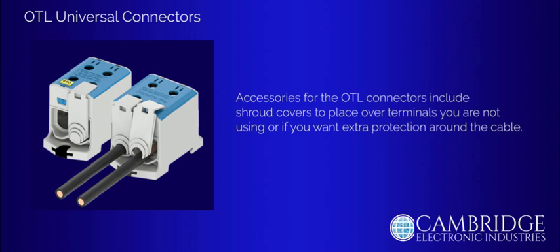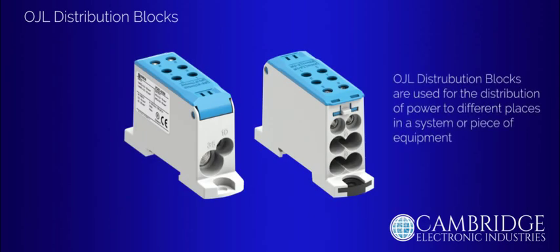Accessories for the OTL connectors include shroud covers to place over terminals you are not using, or if you want extra protection around the cable. The OJL distribution blocks are similar to the OTL connectors, but instead of connecting power sources, they are used in the distribution of power to numerous different places in a system. They can be used in conjunction with the OTL connectors or as a standalone product.